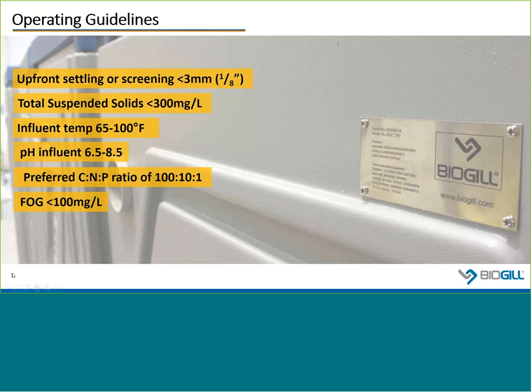Operating guidelines for BioGill systems are pretty simple and consistent with those for other biological treatment processes. BioGill is designed primarily for the removal of soluble organics, so process design should include an upstream screening or settling step to remove larger particles above about 1 to 3 millimeters in size, and influent TSS should be reduced to about 300 milligrams per liter or lower. Influent temperatures are optimally above 65 degrees Fahrenheit, as colder temperatures impede biological growth. For colder climates, many BioGill systems have been located inside insulated structures. pH entering the BioGill should ideally be in the neutral range, and BioGill can handle fats, oils, and greases ideally at levels below 100 milligrams per liter.